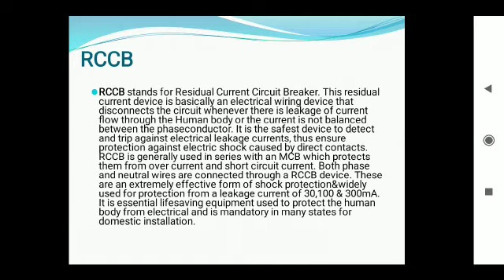Now RCCB. RCCB stands for residual current circuit breaker. This residual current device is basically an electrical wiring device that disconnects the circuit whenever there is a leakage of current flow through the human body or the current is not balanced between the phase conductors. It is the safest device to detect and trip against electrical leakage currents. Thus, it ensures protection against electric shock caused by direct contact.